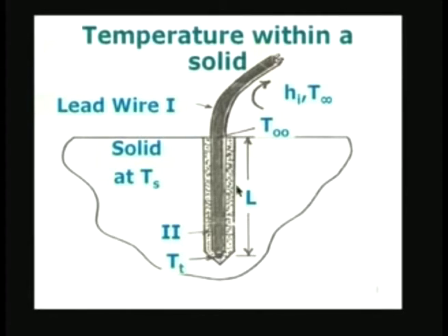So, we can use some material which conducts heat effectively, so that there is a good thermal contact between the thermocouple and the walls of the hole drilled into the material. We will see how it is going to affect the measurement of temperature. And of course, the lead wire has to be taken out, there is no other way. The thermocouple lead is taken out and it is exposed to an ambient at T infinity, that is shown here, and maybe some amount of convective heat transfer is taking place between the outside of the lead wire and the ambient.